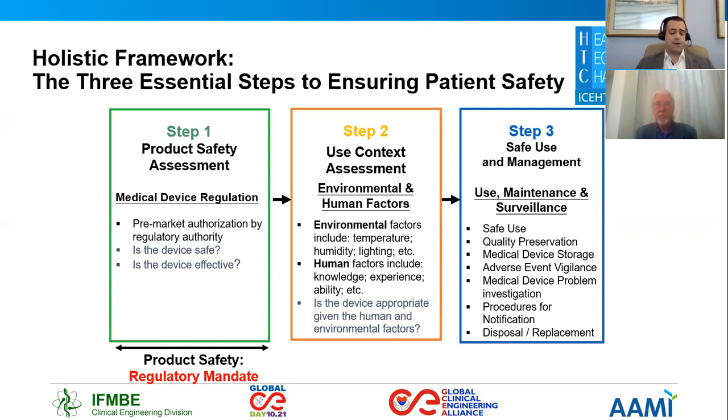They function by requiring manufacturers to carry out, amongst other things, an assessment of provision of instructions for safe use, protocols for preservation or maintenance of the quality of the device, including in the delivery process to the customer or the end user, and to conduct post-market surveillance, adverse event reporting, corrective action, and preventative action. After delivery, the device is possessed by the user, and it is the user who must take up the responsibility to ensure that they follow safe use instructions, maintain device quality, and monitor device performance.